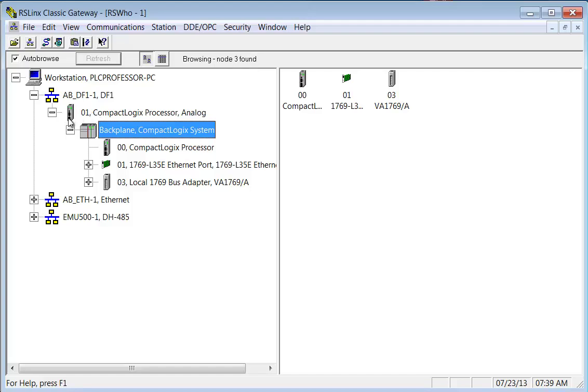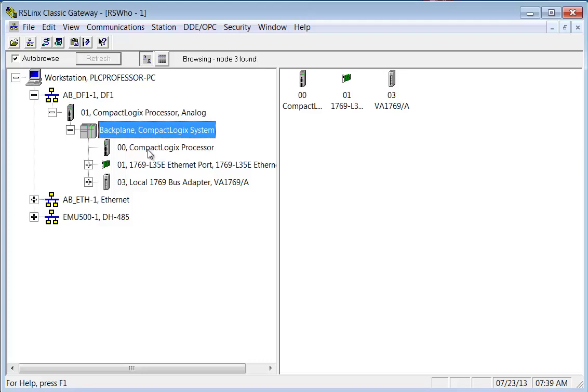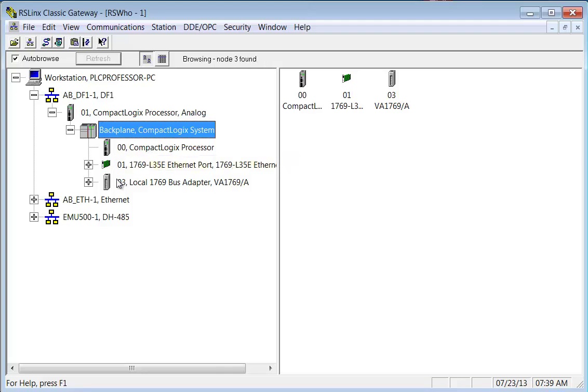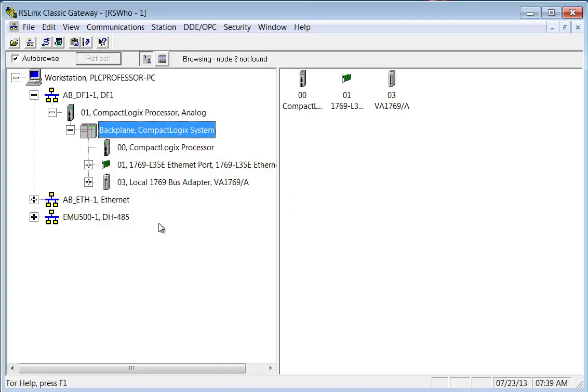So this is like a graphical placeholder to show you what's in slot 0, but this is actually the processor as far as RSLinx goes. So you come in that little connector there on the bottom of the processor which is RS-232. You go out the back of the processor onto the backplane, and on the backplane you can look, turn around and look back the way you came and see the processor, or you can travel on down the backplane and you see a L35E Ethernet port and a 1769 bus adapter. These are all things on the backplane.